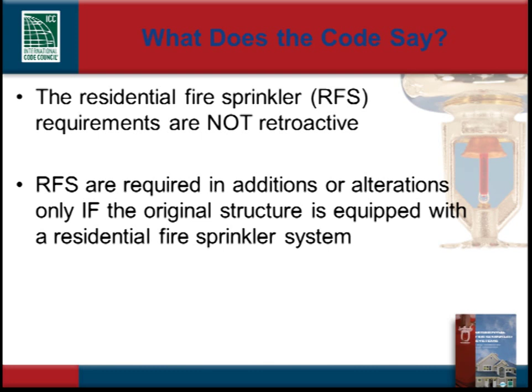The requirement for residential fire sprinklers is not a retroactive requirement — it is written to apply to new construction. The only time the residential fire sprinkler requirement would be applied to an existing dwelling is when the owner decides to construct an addition or remodel and the dwelling is already equipped with a residential fire sprinkler system. In those cases, the system would need to be extended or modified where necessary, based on the extent of the new construction.